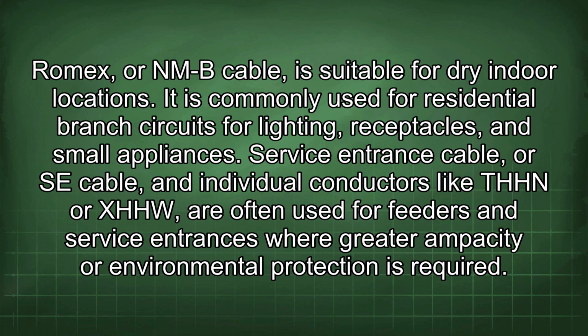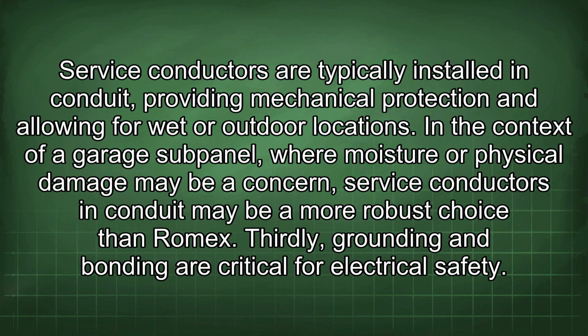Service entrance cable, or SE cable, and individual conductors like THHN or XHHW are often used for feeders and service entrances where greater ampacity or environmental protection is required. Service conductors are typically installed in conduit, providing mechanical protection and allowing for wet or outdoor locations. In the context of a garage subpanel where moisture or physical damage may be a concern, service conductors in conduit may be a more robust choice than Romex.